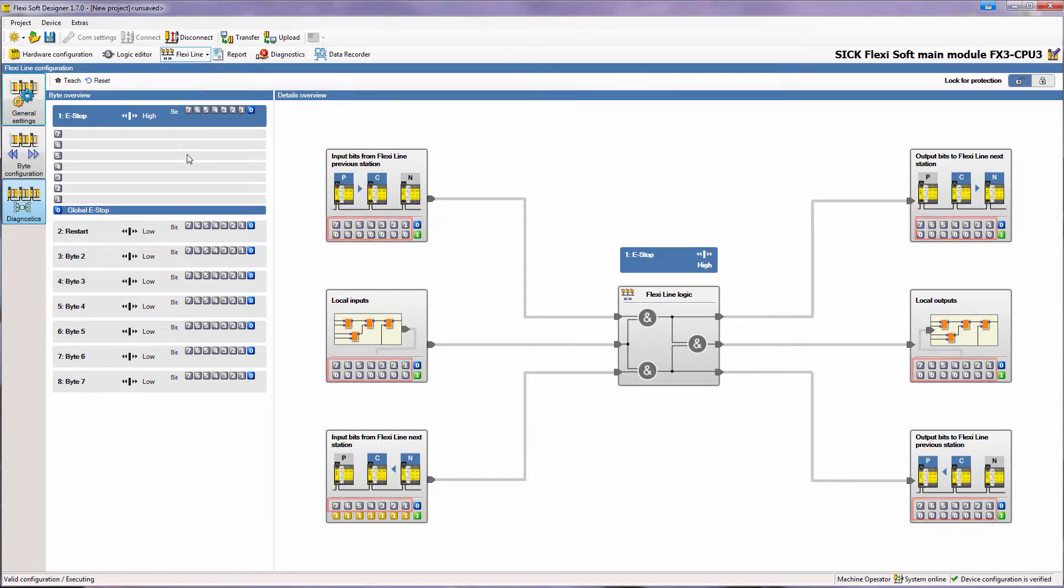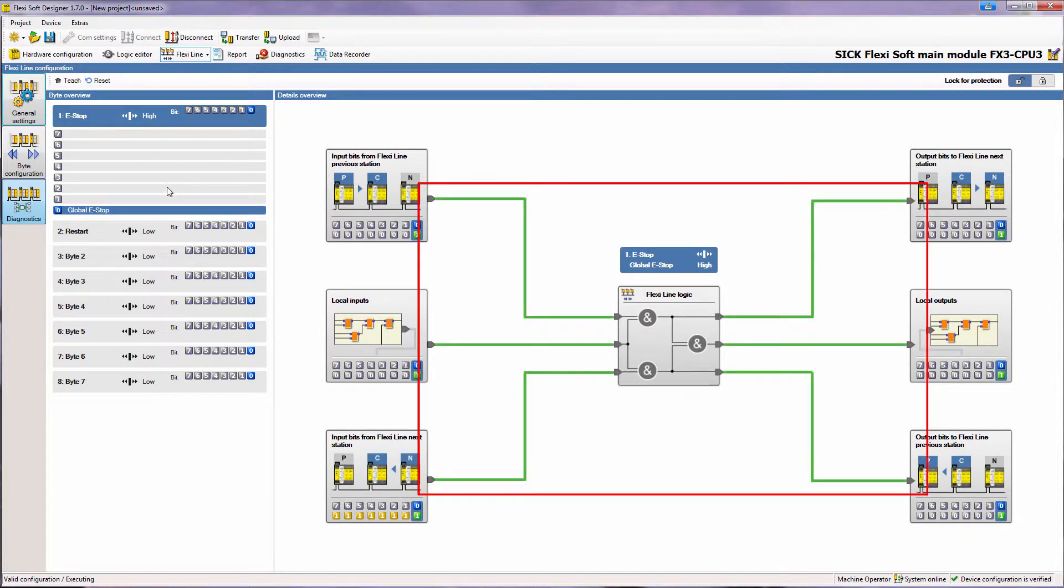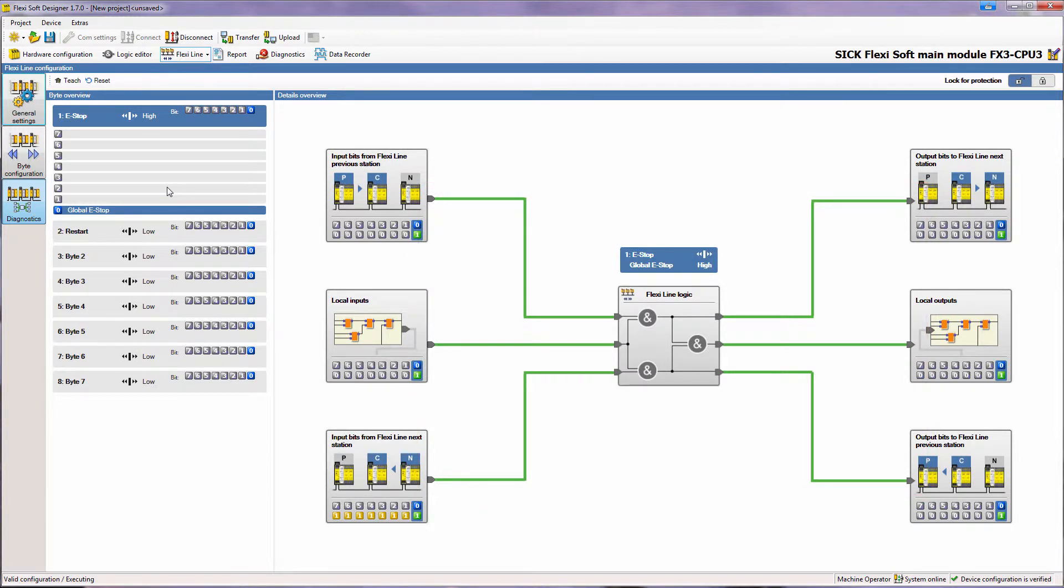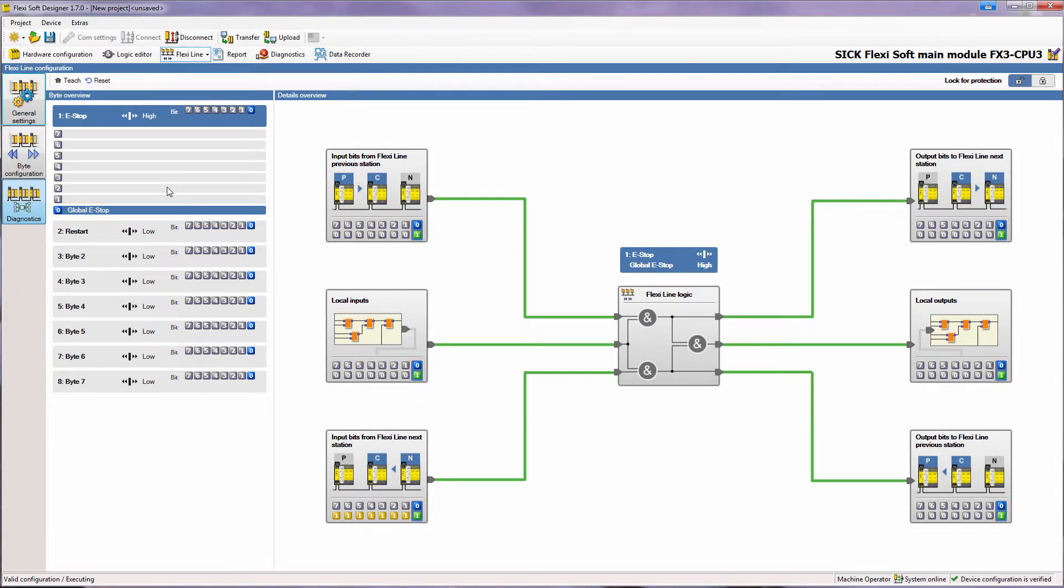If I select a single bit in the byte overview, the processing of this bit is shown in detail on the right. Let me explain this in combination with the demo cases and the global e-stop function. I select the bit global e-stop and the background of this bit in the details overview gets blue. At the moment no e-stop of any demo case has been actuated, so the local e-stop bit as well as the e-stop bits from the neighboring stations are high and therefore displayed in green.